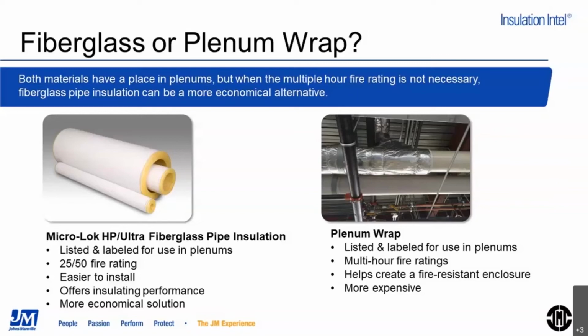But if you're running plastic pipe, you can use it for DI water or RO water instead of stainless steel. You put the HP Ultra on there and you can continue. Now you've got your 25/50 rating and you're using plastic pipes, which is a big benefit, especially with the price of stainless steel going up.